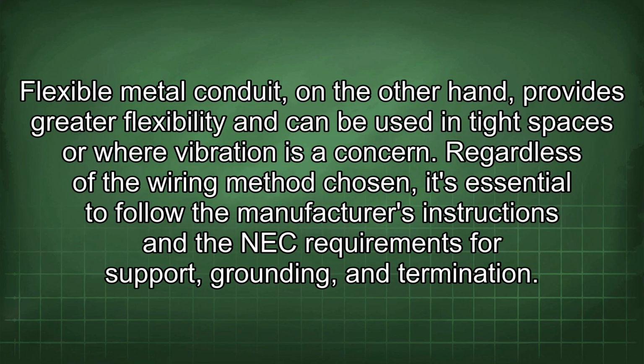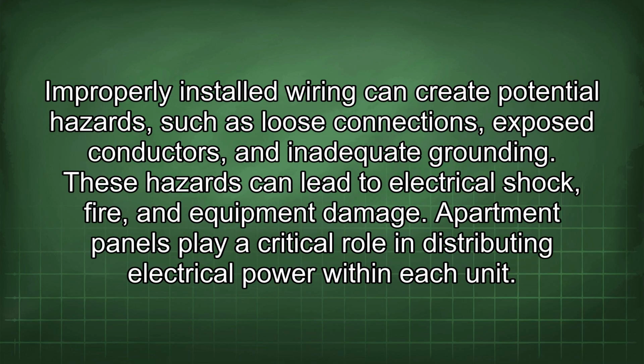Flexible metal conduit, on the other hand, provides greater flexibility and can be used in tight spaces or where vibration is a concern. Regardless of the wiring method chosen, it's essential to follow the manufacturer's instructions and the NEC requirements for support, grounding, and termination. Improperly installed wiring can create potential hazards, such as loose connections, exposed conductors, and inadequate grounding. These hazards can lead to electrical shock, fire, and equipment damage.